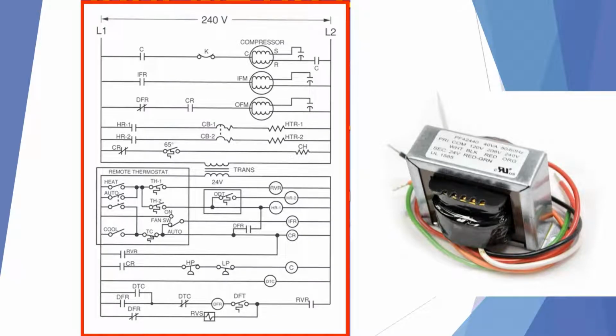This is the most common type of transformer that is found in HVAC work. This is a multi-tap transformer, which, depending on which wires we connect together, we can get 120 volts, 208 volts, or 240 volts on our primary side with a 24 volt secondary. So in a lot of our HVAC application, we have 240 volts that is applied to a transformer on the primary side, and then we have 24 volts on the secondary side, which does all of our control on our relays.